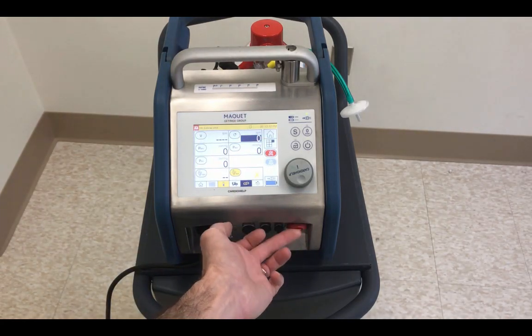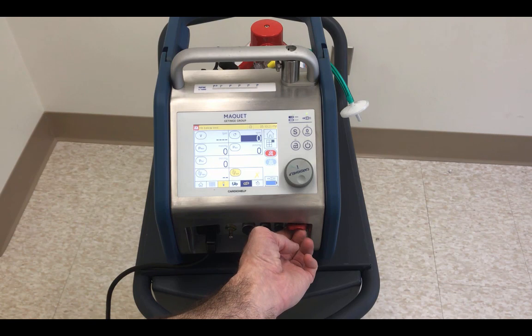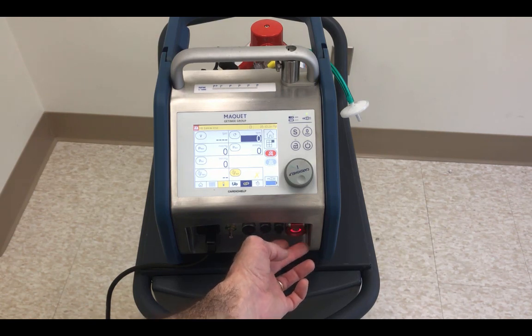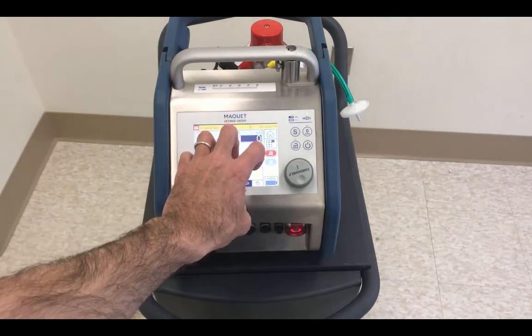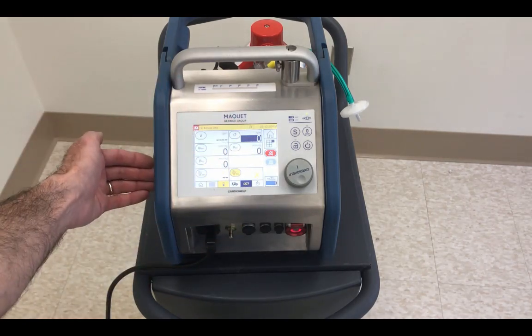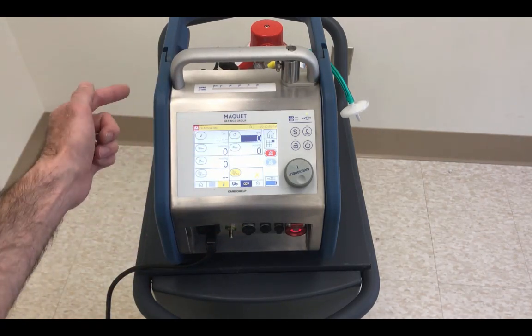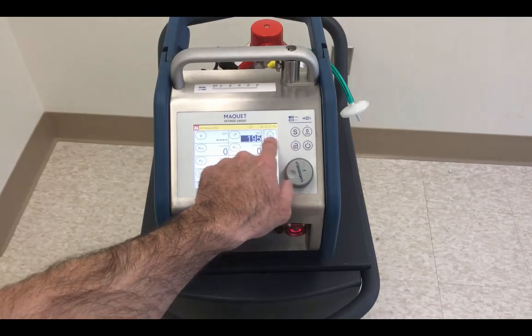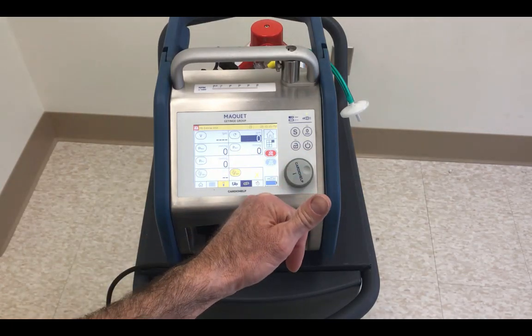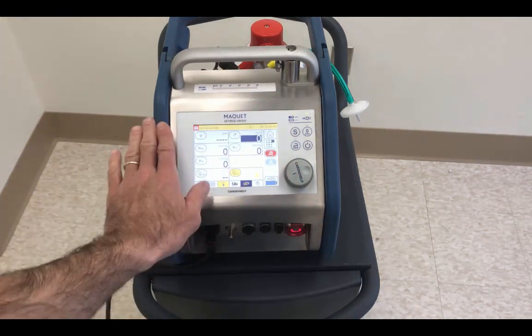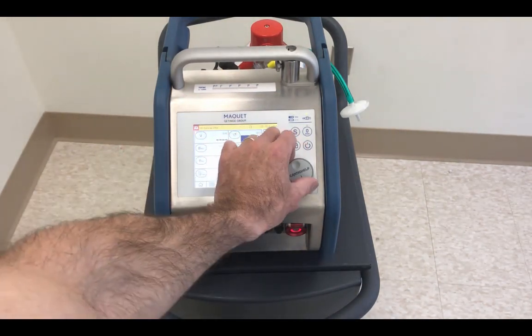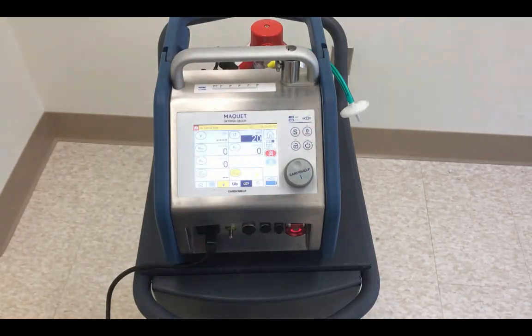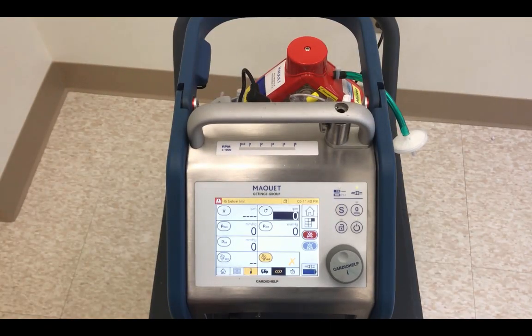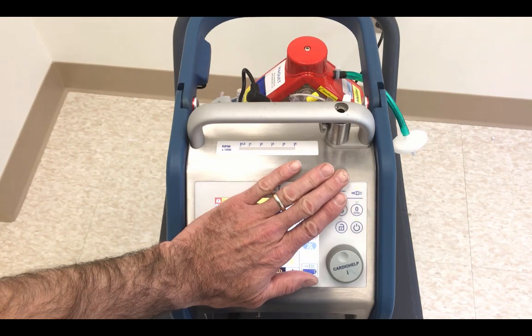Therefore, they give you this button, and if you press and hold this button for the right period of time, it will turn off the screen, and it will disengage the CPU. And then what you have is just a dumb pump. You've got a knob that controls RPMs, and it's entirely up to you. You'll have no data because the screen is dead. You'll have no alarms. You'll have no limits. You'll have no safety. But you've got a knob that you can turn up and down and control your flow. You might wonder that if you lost the screen, how would you have any idea what you're flowing? How would you know when to stop turning the knob?